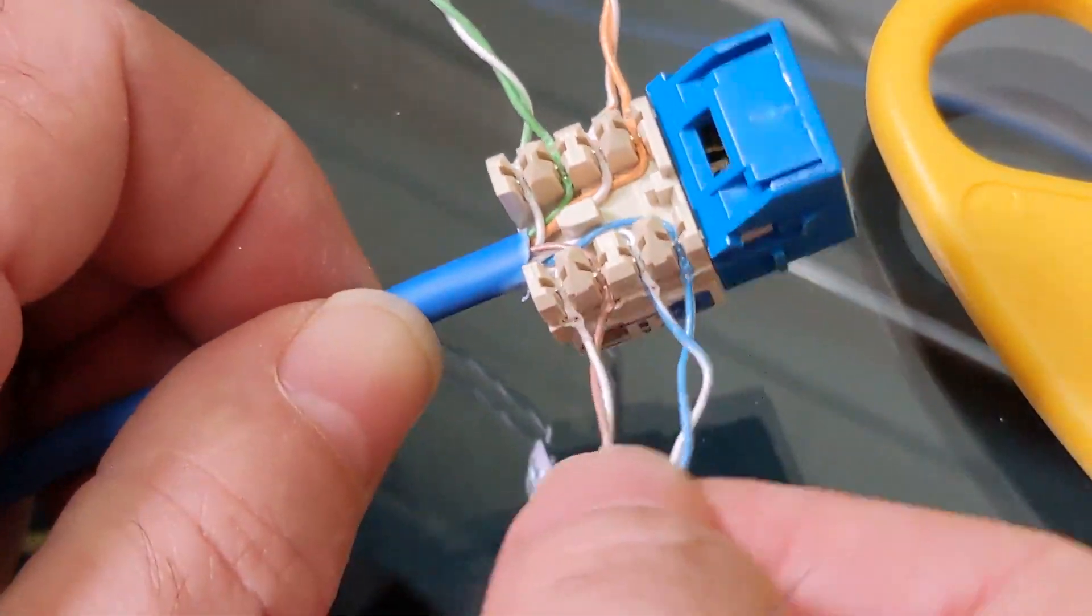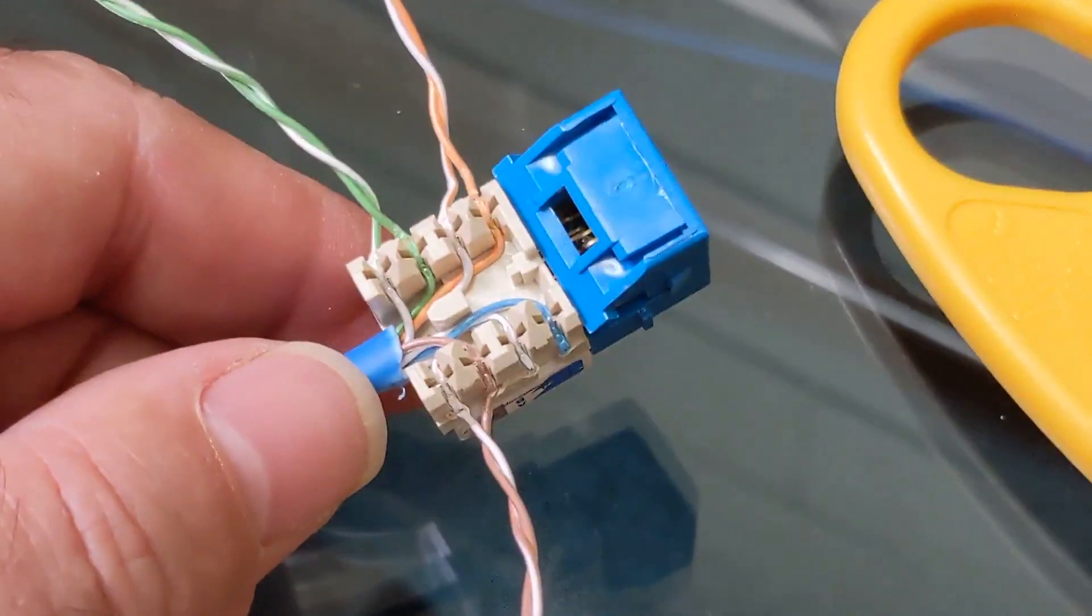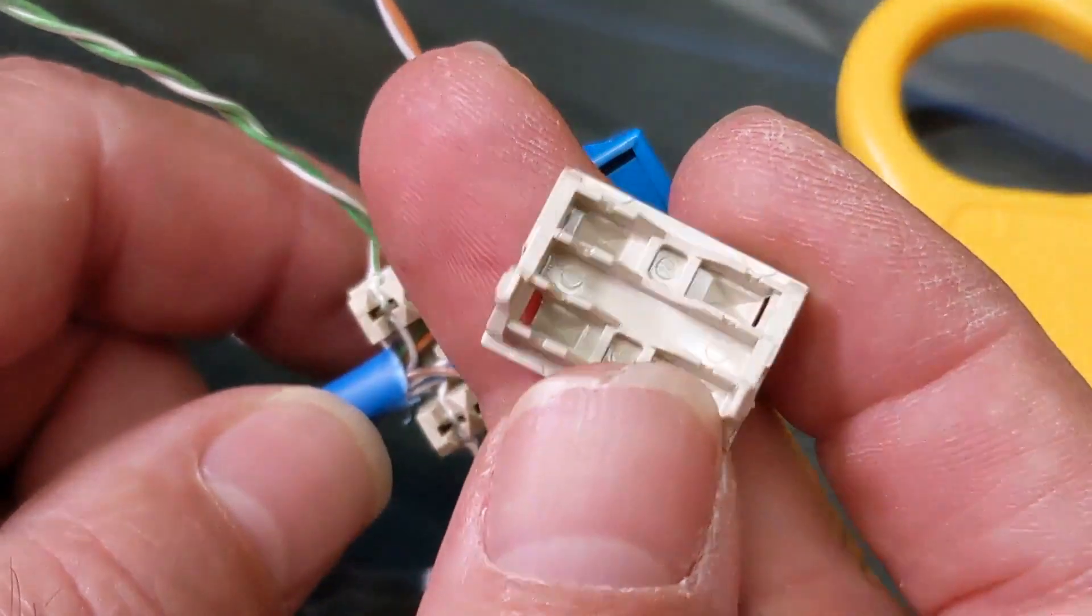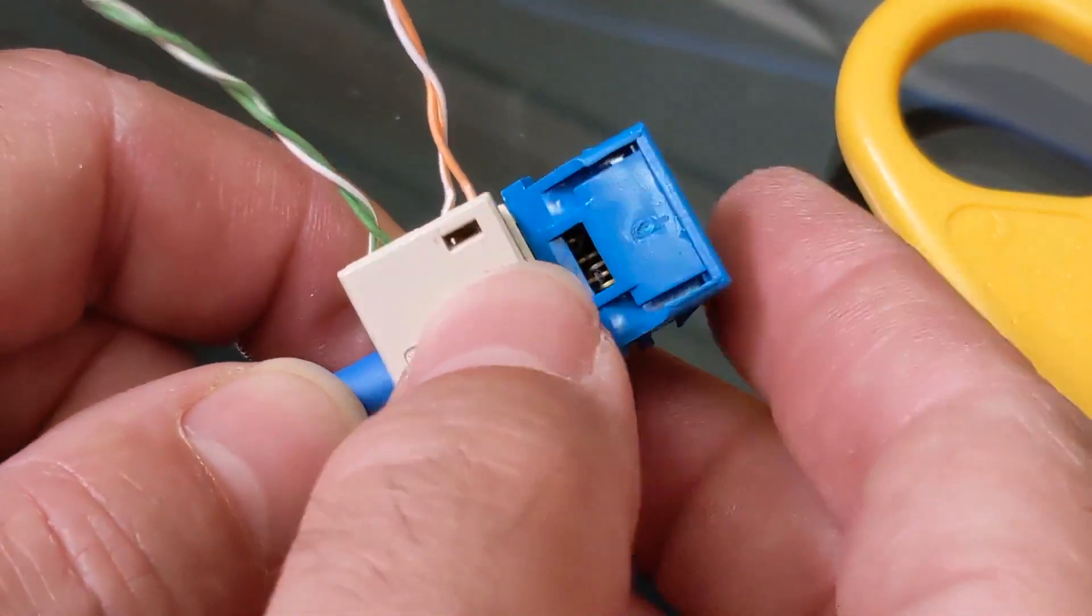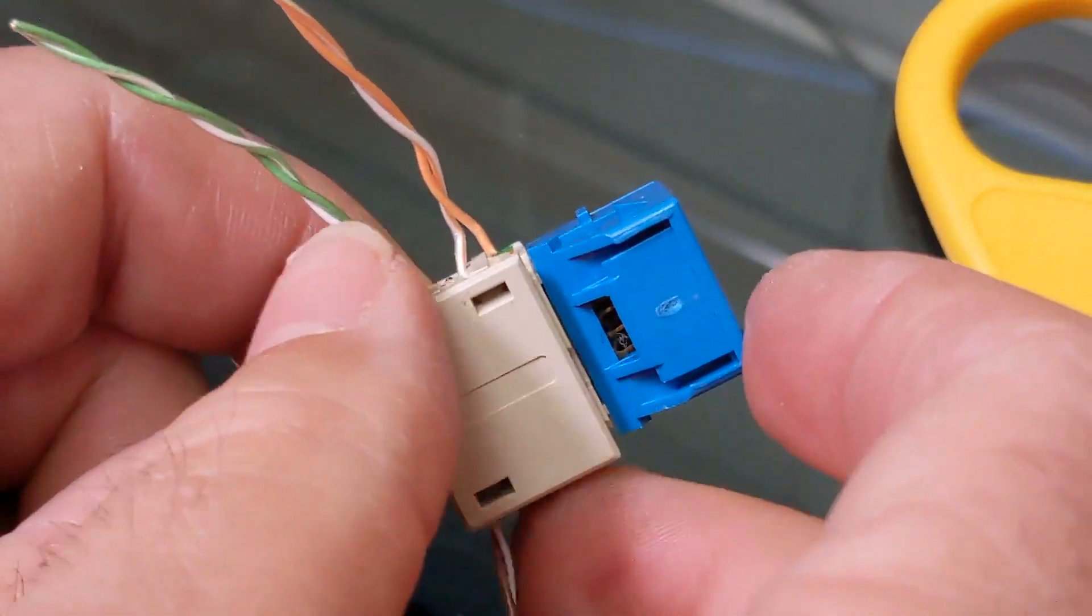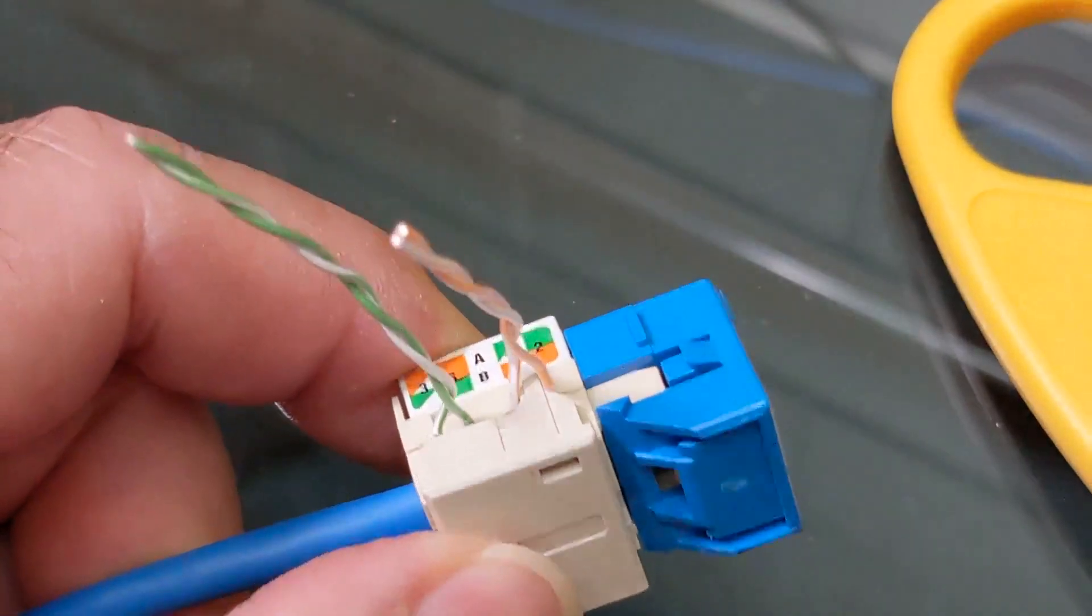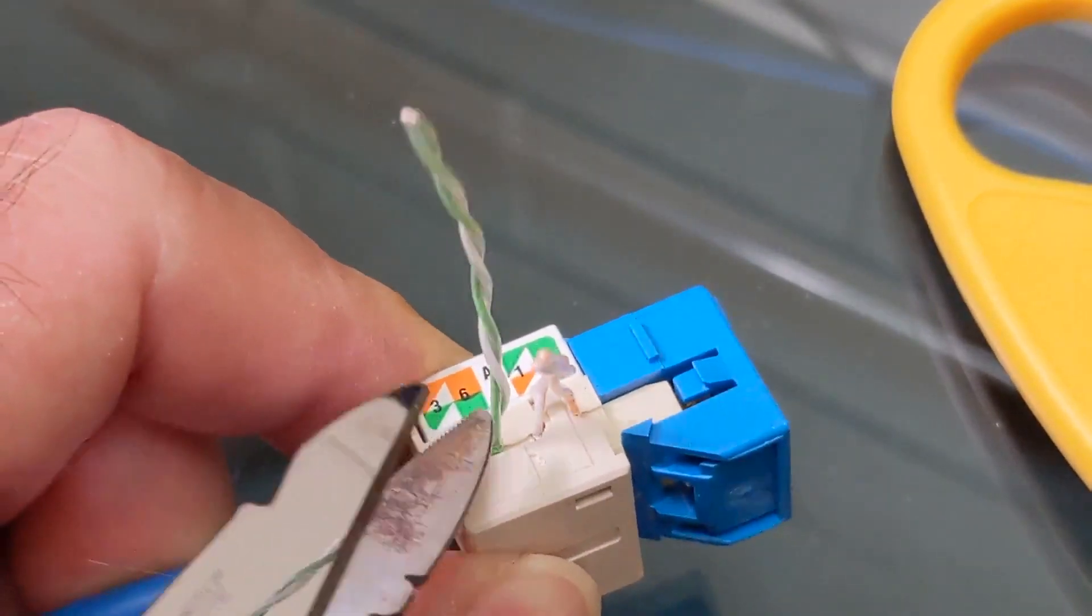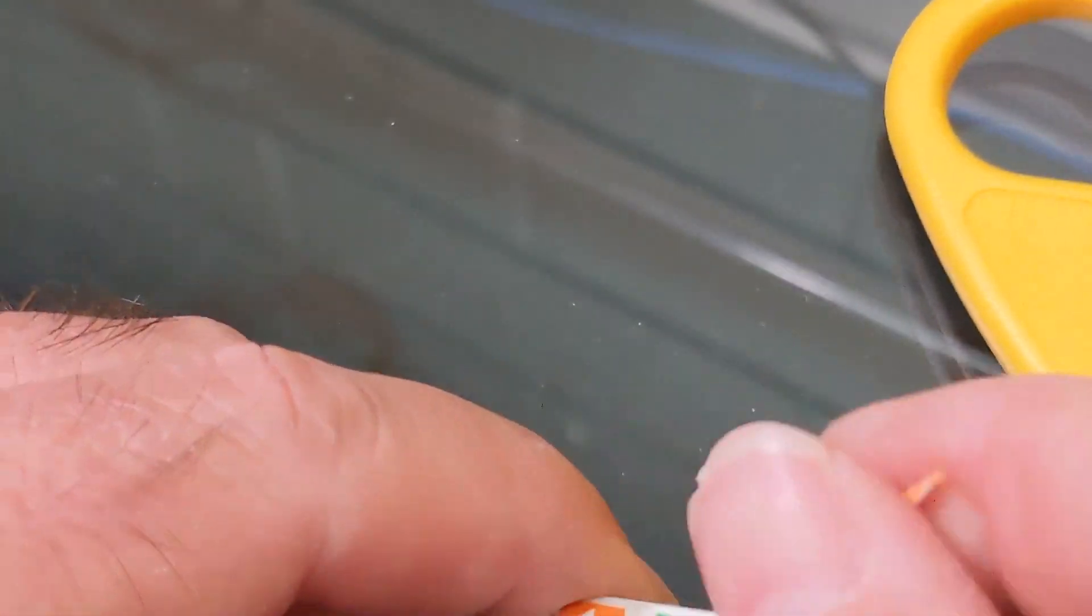Now like I said, it either cuts them off, or at the very least it perforates them, so you just wiggle them off. If you don't have the impact tool, what you can do is take what they call the dust cover. If you take and lay your wires out like I just did, and push the dust cover in real tightly, there's little wire guides in there that should force the wires down to the bottom of the slots. Then you can come back with your scissors and, as close as you can get, snip off the excess, because you don't want any excess hanging out when you're done.